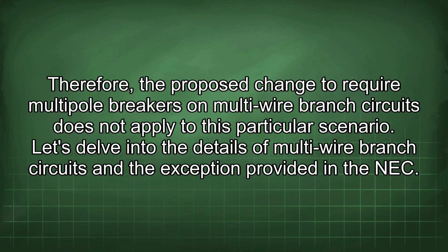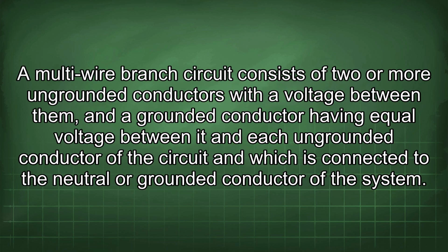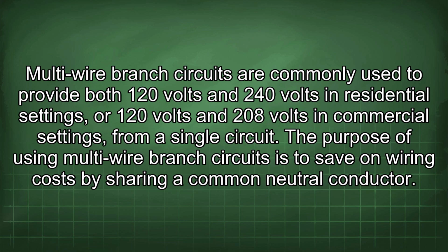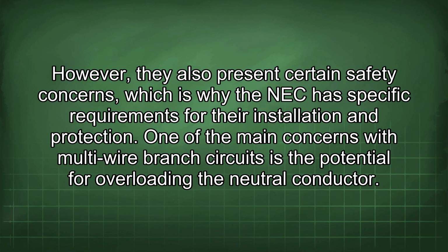Let's delve into the details of multi-wire branch circuits and the exception provided in the NEC. A multi-wire branch circuit consists of two or more ungrounded conductors with a voltage between them, and a grounded conductor having equal voltage between it and each ungrounded conductor of the circuit, and which is connected to the neutral or grounded conductor of the system. Multi-wire branch circuits are commonly used to provide both 120 volts and 240 volts in residential settings, or 120 volts and 208 volts in commercial settings, from a single circuit. The purpose of using multi-wire branch circuits is to save on wiring costs by sharing a common neutral conductor. However, they also present certain safety concerns, which is why the NEC has specific requirements for their installation and protection.